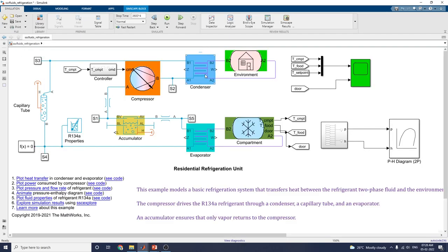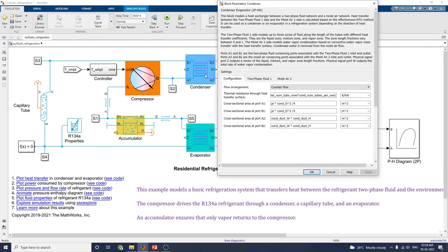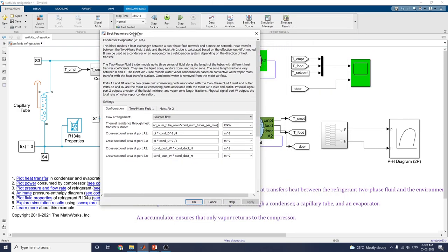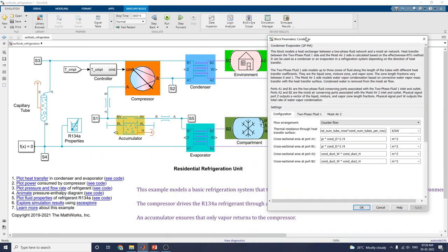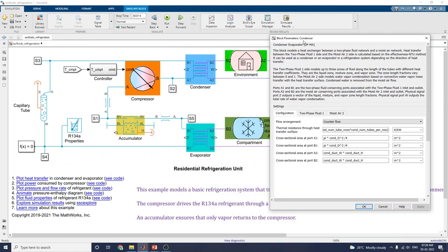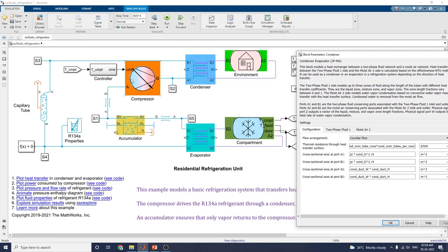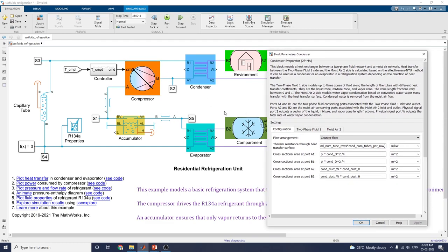These are the condenser blocks. The condenser/evaporator block implements a heat exchanger between the two-phase fluid network and a moist air network. Heat transfer between the two-phase fluid on one side and moisture on the other side is calculated based on the effectiveness NTU method. It can be used as a condenser or an evaporator in a refrigeration system depending on the direction of heat transfer.